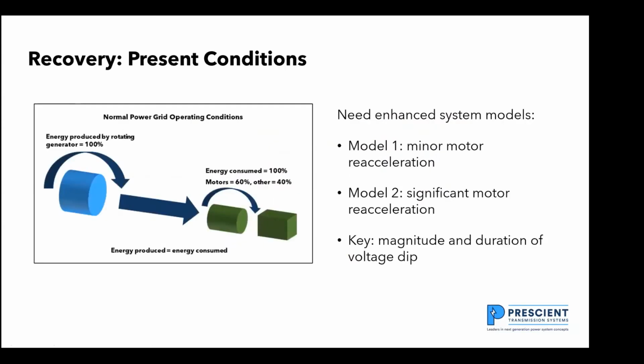I'm looking at recovery conditions, and that's what we're really focused on, preventing wide area blackouts by understanding the recovery conditions. Generators producing 100% power, the motors are consuming on the order of 60% power, and other loads are consuming 40% power. When a fault occurs, the existing models show minor motor reacceleration, and we're recommending that you have significant motor reacceleration. And the way you've determined that you need significant motor reacceleration is you have to understand the geographical spread of the voltage dip.